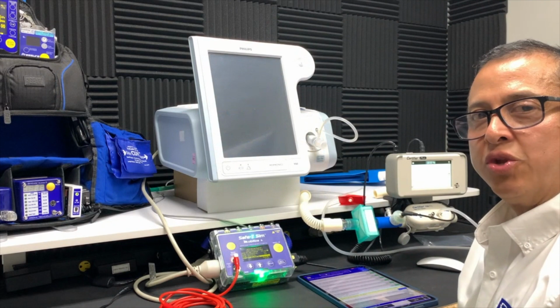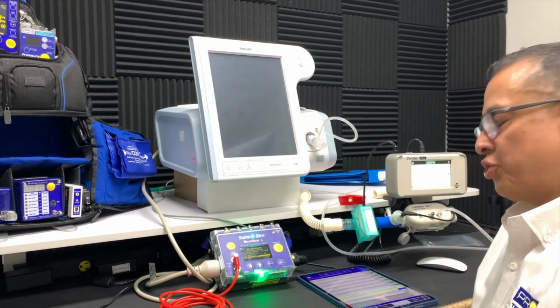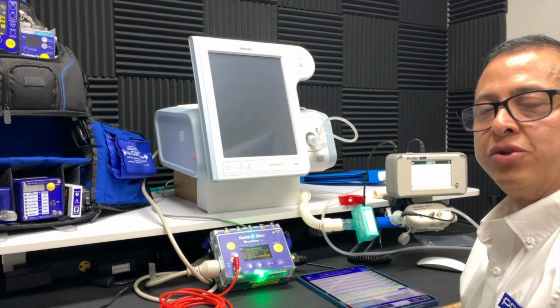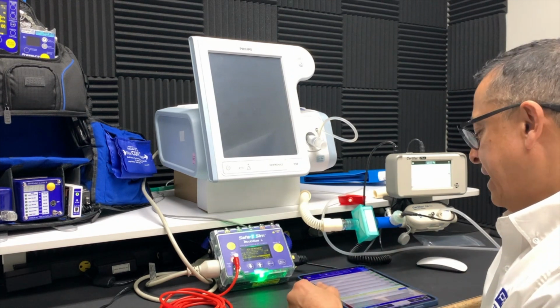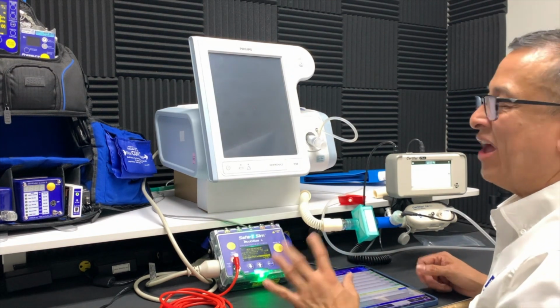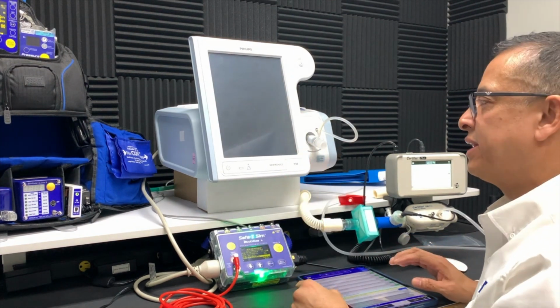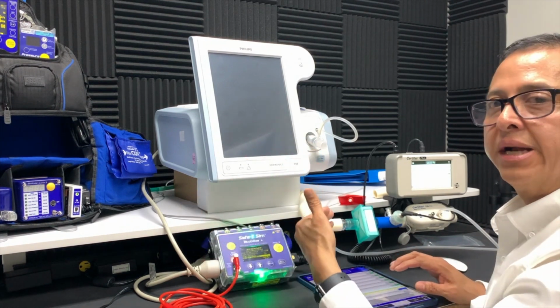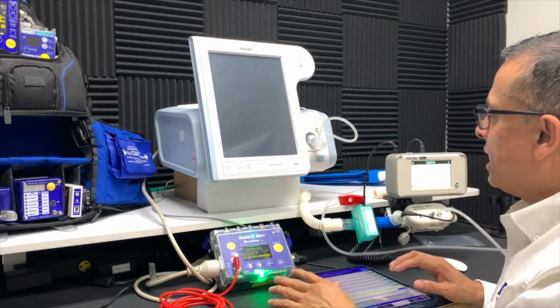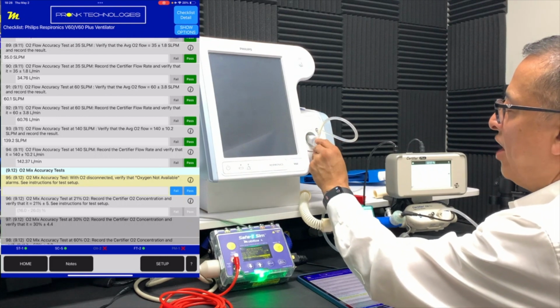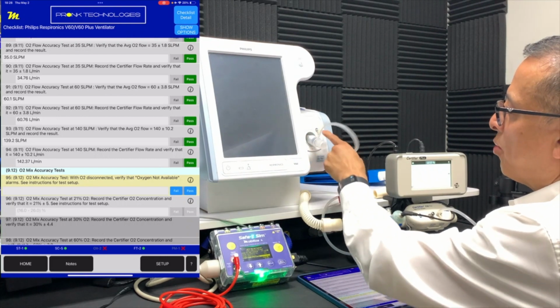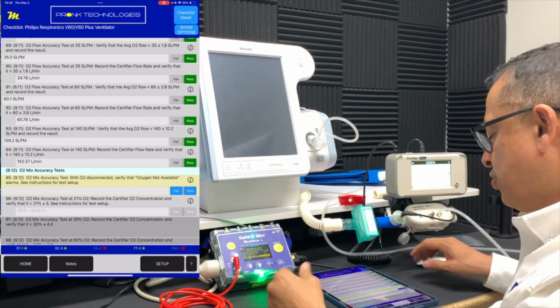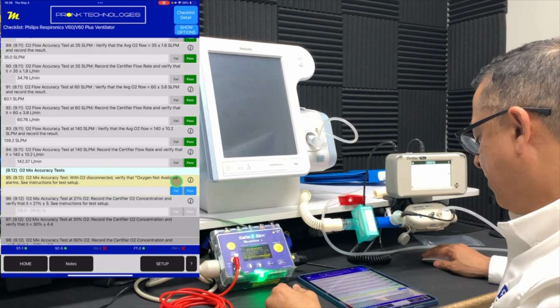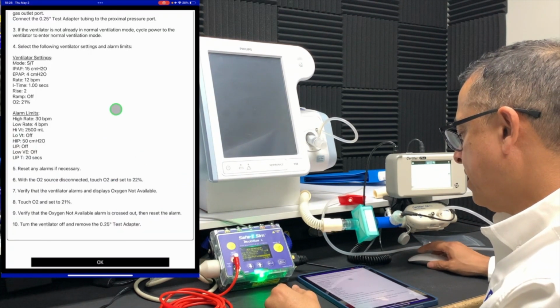So next, we need to do our O2 mix accuracy tests. And to do this, we first need to do an oxygen not available test. It's a safeguard test to make sure that the ventilator can detect that oxygen is not coming in, so it's important that we do that. And it requires us to connect the pick-off valve to it and connect it to the proximal pressure port and to run that test.